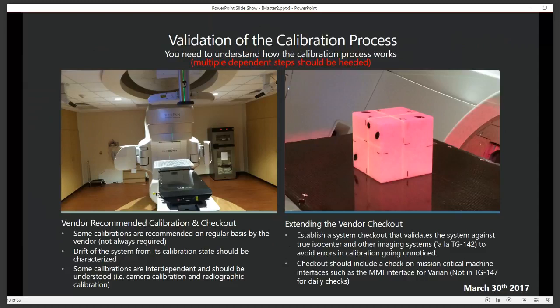My centers, I haven't currently calibrated my cameras for 24 months. It does not drift away from that. So what we do is we do a calibration verification every month, but we do not recalibrate, because it is an interdependent step in the radiographic calibration. And so if you recalibrate monthly when you don't need to, you've now invalidated your radiographic calibration for SRS.